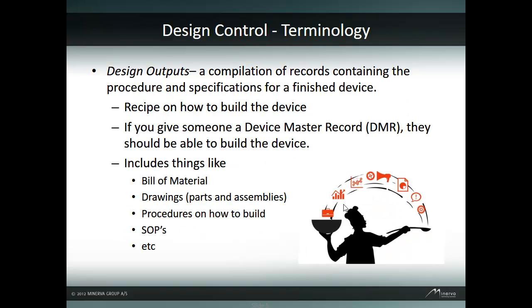Design output is a compilation of records containing the procedure and specification for the finished device. In other words, it's a recipe on how to build a device. This is also known as the device master record. If you gave someone the device master record, they should be able to build a device. The design output and DMR include things like bills of material, drawings of parts and assemblies, instructions on how to assemble and build a device, standard operating procedures, and much more.